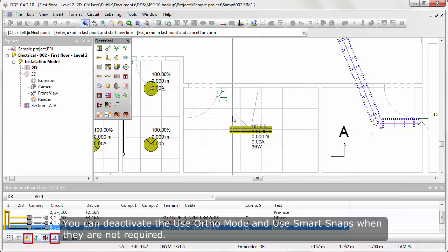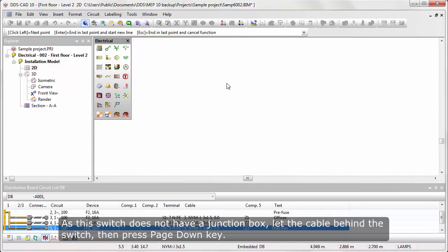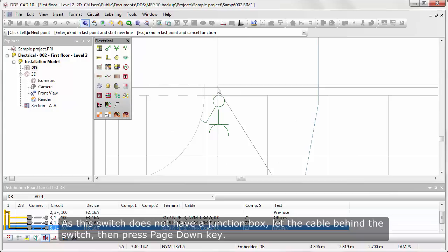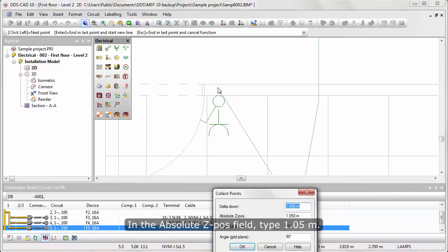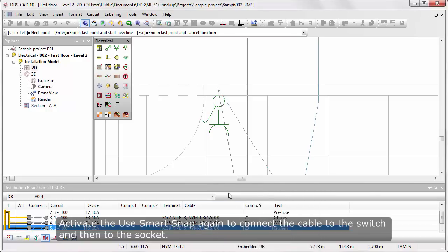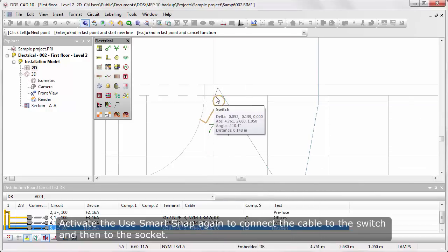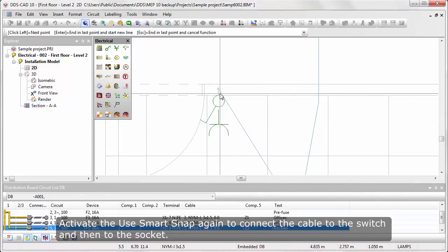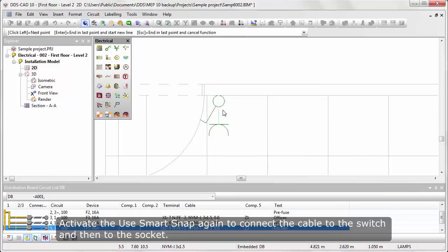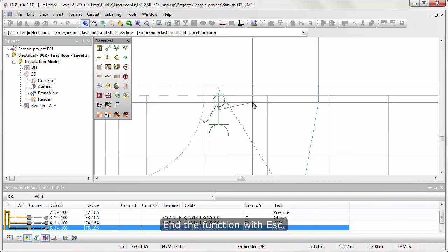You can deactivate the Use Ortho Mode and use Smart Snaps when they are not required. As the switch doesn't have a junction box, let the cable behind the switch, then press Page Down key. In the Absolute Z-pos field, type 1.05 meters. Activate the Use Smart Snaps again to connect the cable to the switch and then to the socket. End the function with Escape key.